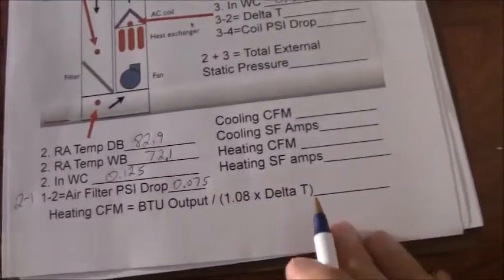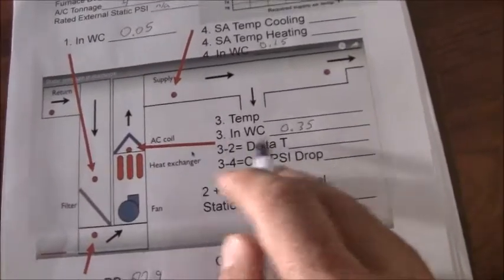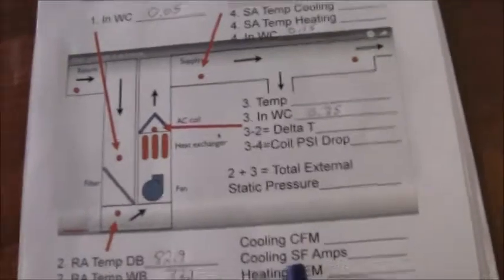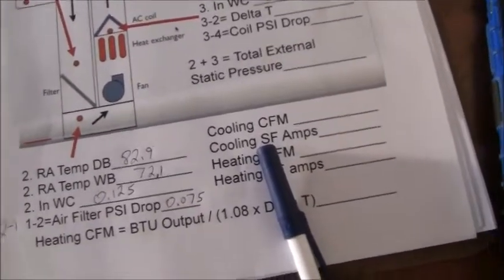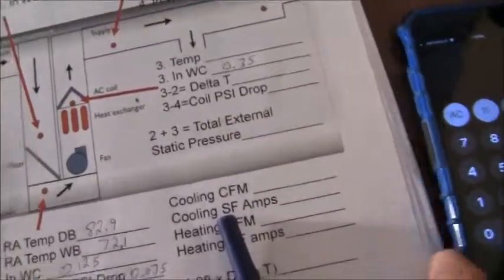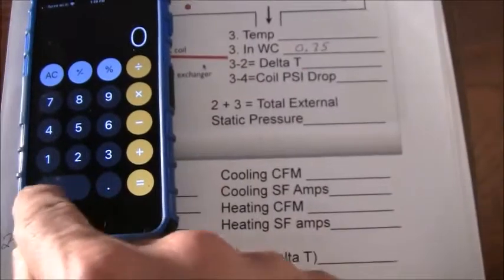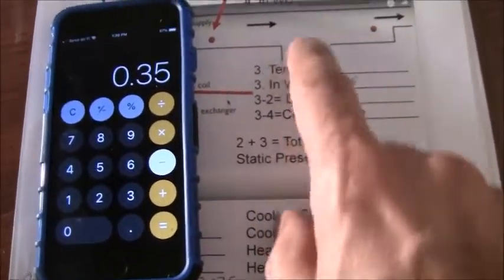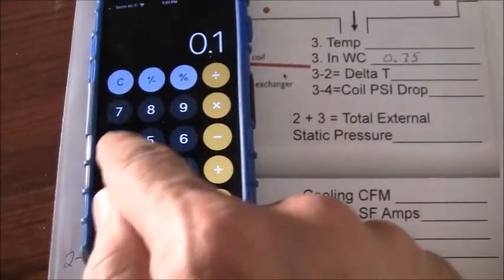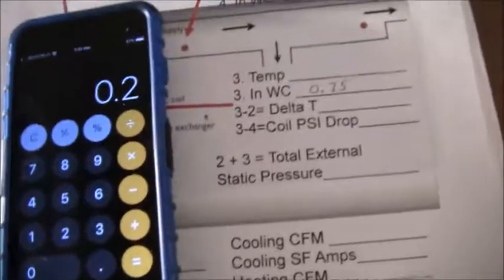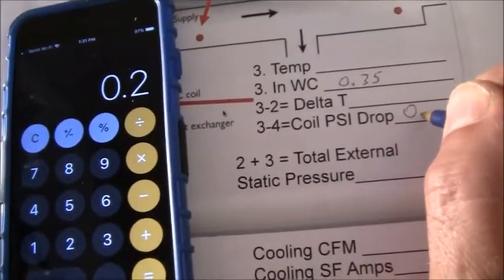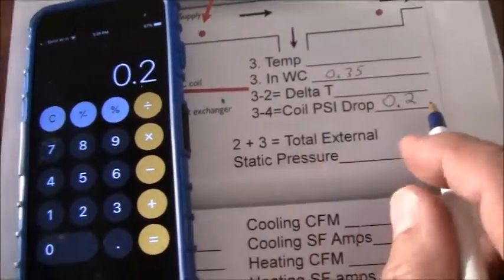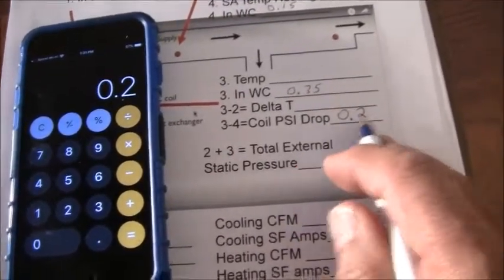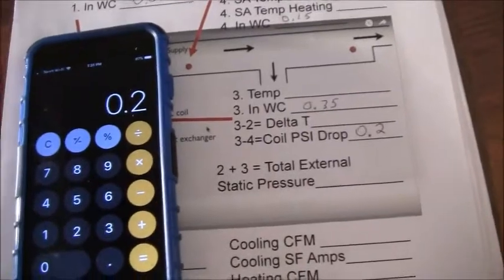Now, we can determine the coil pressure drop by taking point number 3 and subtracting point number 4 from it. So let's go ahead and do that, just like we did the other one. We take point number 3, 0.35, and subtract point number 4, which is 0.15. That's going to equal 0.2. So we know that the coil pressure drop is 0.2 inches of water column, okay? So that's not a bad pressure drop across the coil. The coil is not plugged, producing a restriction of airflow.